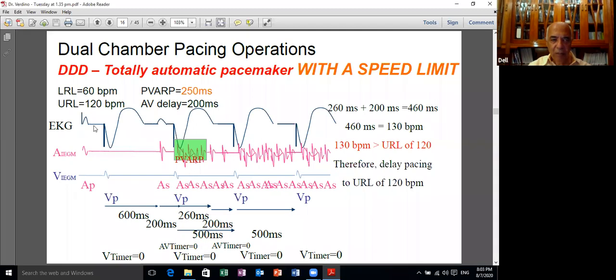After the first 100 or 120 milliseconds, there is another period called the safety pacing period. In this safety pacing period, if the ventricle senses an activity, it paces one beat. So it again avoids the occurrence of crosstalk. So crosstalk is obviated by 2 intervals. The first is the absolute blanking period in the initial part, which follows a sensed or a paced atrial activity, and then a crosstalk window with safety pacing. And then the last part of the AV interval is the 3rd component, which is an alert period in which ventricular activity is sensed, to give space for the natural ventricular activity or the paced ventricular activity to occur.